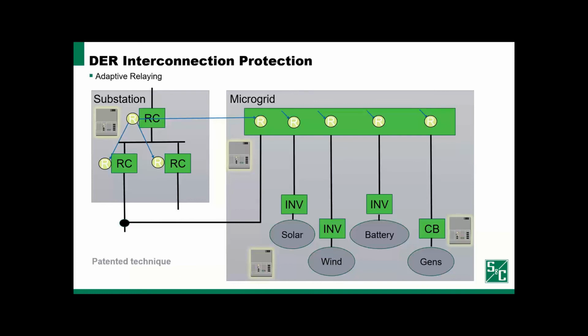Now, one approach that we've used to success in several past microgrids is a staggered approach where we change some protective settings immediately prior to making a transition from grid tied to islanded or from islanded to grid tied. And then we change the remaining settings as soon as that transition occurs. This staggered approach ensures that the system is protected throughout the transition, which is a key critical time for the microgrid. Now, this particular approach that I'm describing is something that we've applied for and successfully patented in the United States.